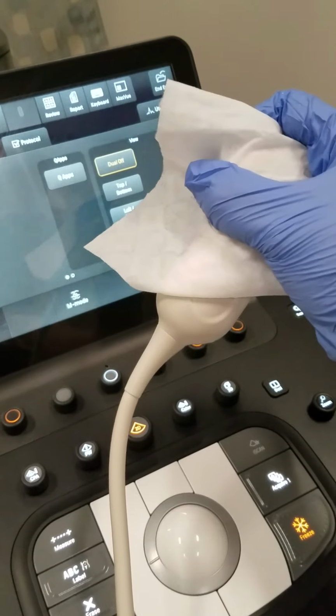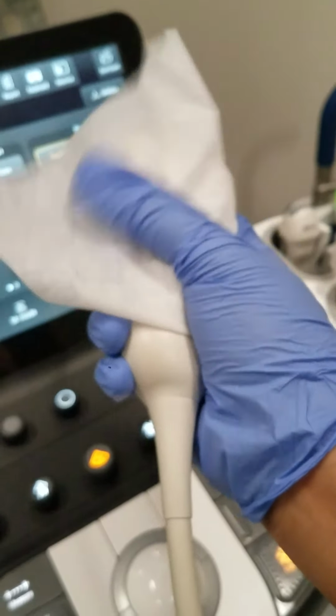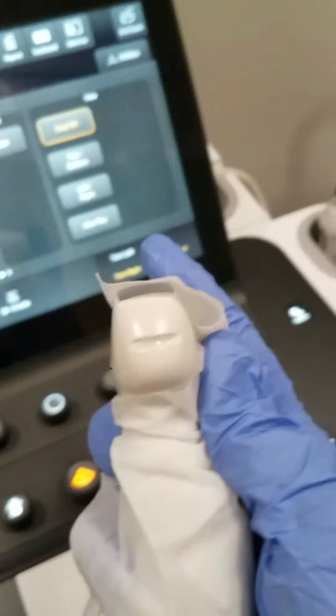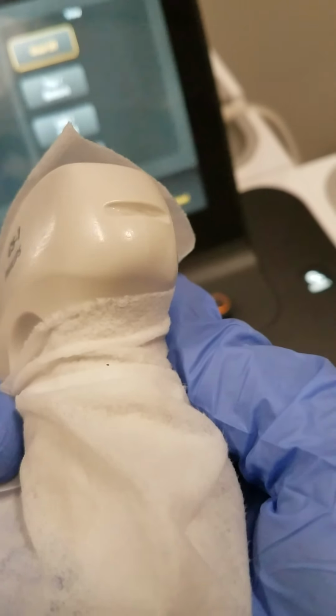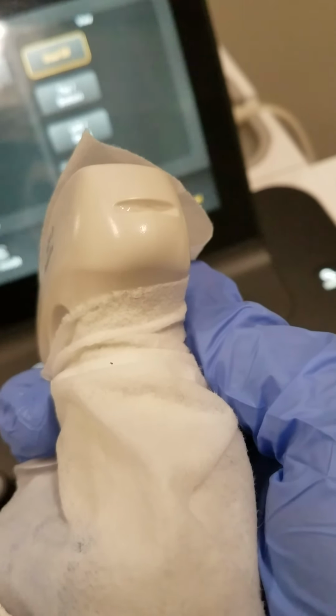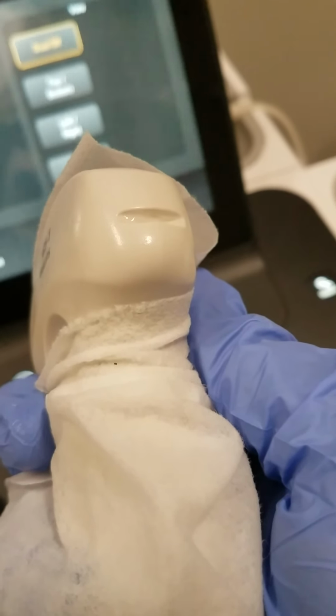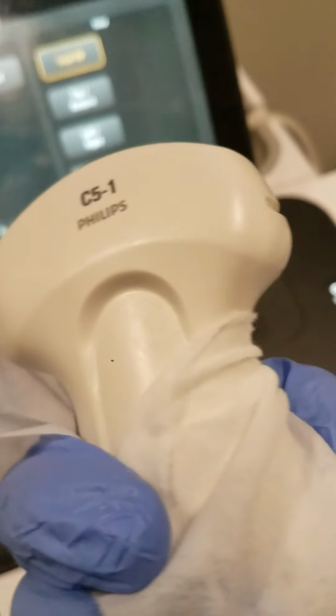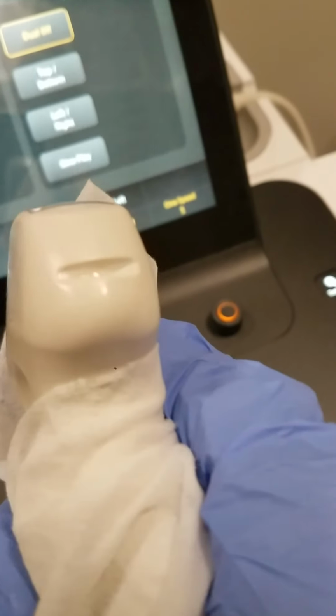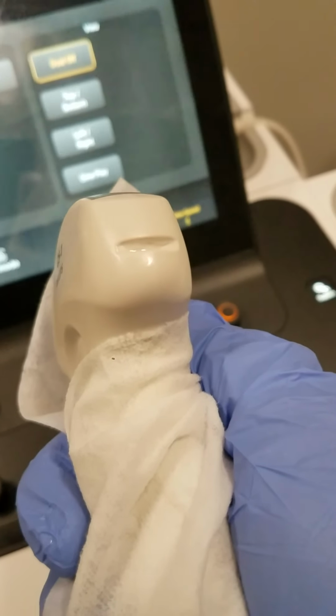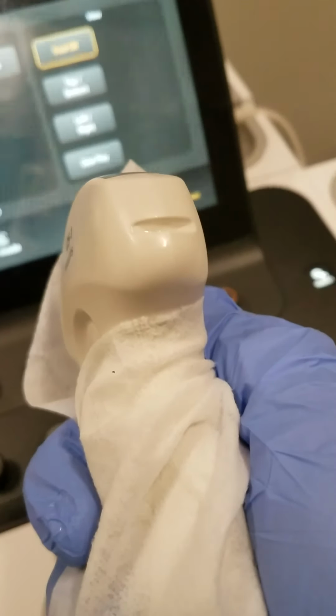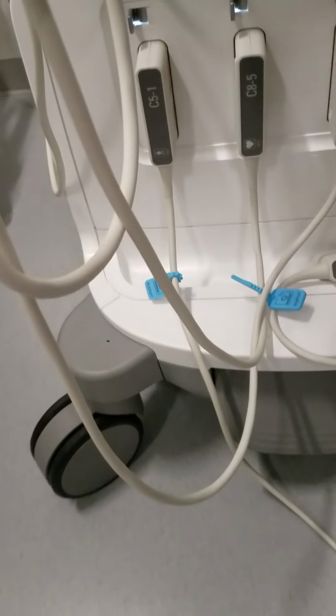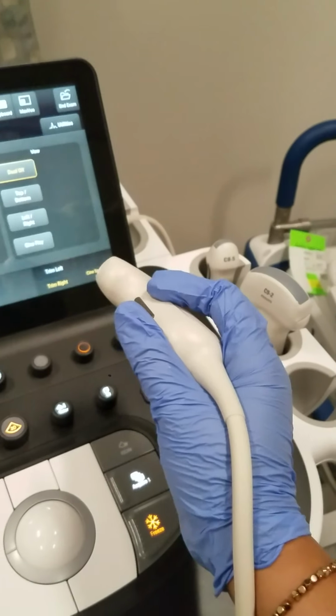When you clean your transducer, you want to make sure you clean every part of your transducer, to include the top. And if you notice closely, there's a little notch there. Do you see the gel that's in there? A lot of times sonography students and sonographers miss that portion on a probe, and that gel could possibly be transferred from patient to patient. So make sure you clean that part of the probe as well, to include the cord all the way down, potentially to where it is in the port.